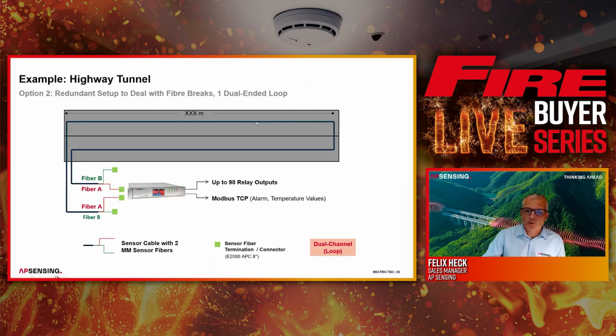If there's an interruption, the controller will take out approximately 20 meters around the cut, and then measure from both sides up to the cut, and the controller will signal system fault or sensor cable fault. This can then be fixed by just splicing the sensor cable, and the controller will go back in operation.